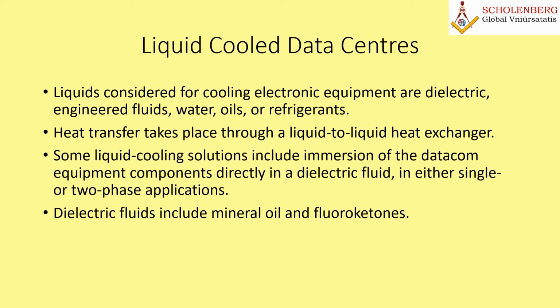Some liquid cooling solutions include the immersion of datacom equipment components directly into the dielectric fluid. In either single or two-phase applications, dielectric fluids include mineral oil and fluoroketones. These are the commonly used liquids for data center equipment cooling.